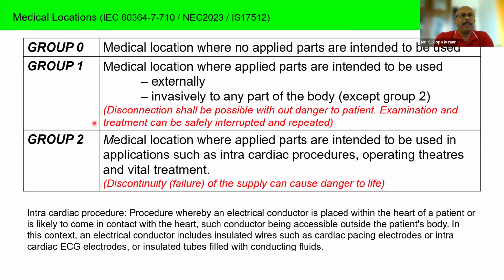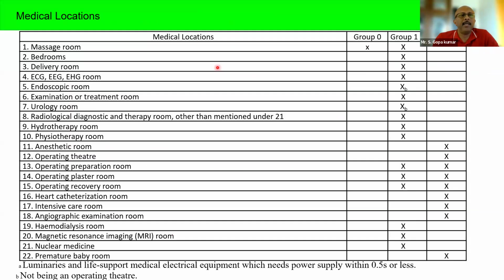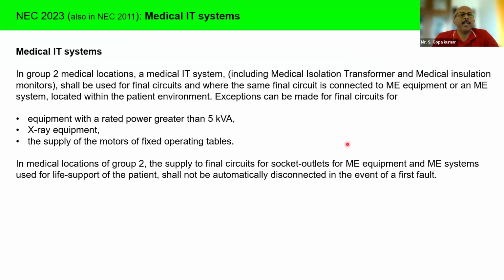Now, coming back to the medical locations. Our standard, National Electrical Code or IS 17512, explained the subject. There are 3 groups of location: Group 0, Group 1, Group 2 location. The explanations are very much given in the standard, and the recommendation of different medical locations, what kind of groups you should set, is also very well explained in the standard. Medical IT system is very critical in Group 2 medical location, especially for equipment that is life-saving, because the disconnection of power supply during the first fault could be dangerous.